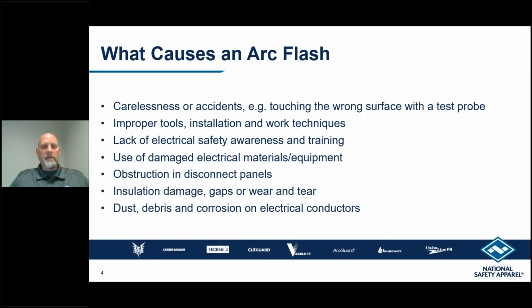What causes an arc flash can be carelessness or equipment malfunction. I've seen arc flash incidents where the cause was determined to be a rodent chewing through a wire at the wrong time. If people aren't properly maintaining their electrical systems, or workers leave tools behind - I saw one investigated incident where someone left a screwdriver behind a bus bar and closed everything up. The next time someone opened that panel, the vacuum caused the screwdriver to fall and land across the bus bar, causing the explosion. So there's no lack of causes for arc flash.